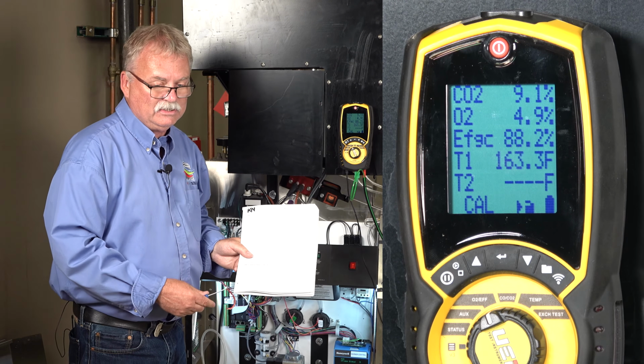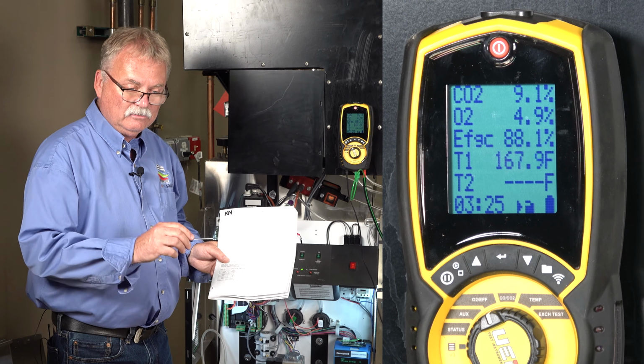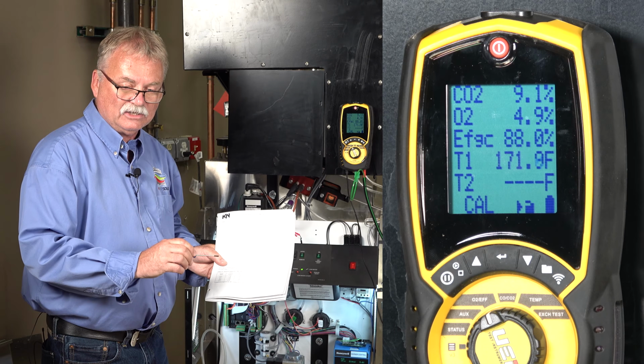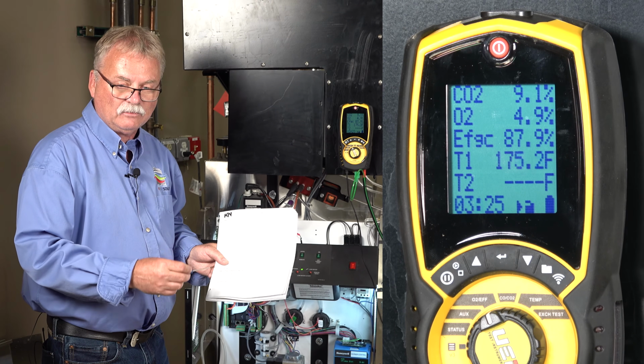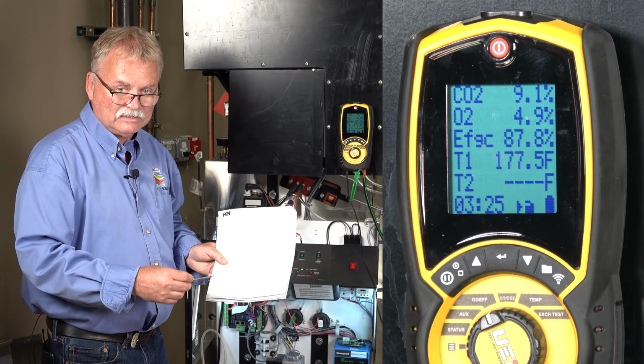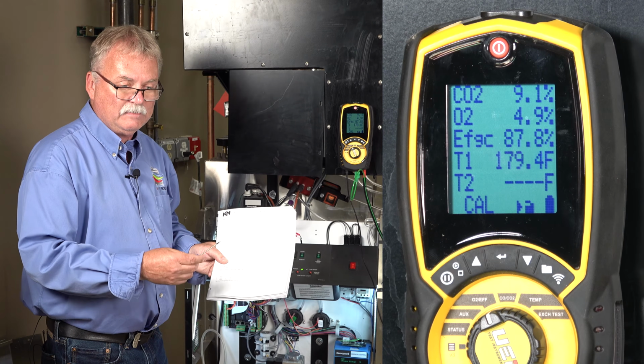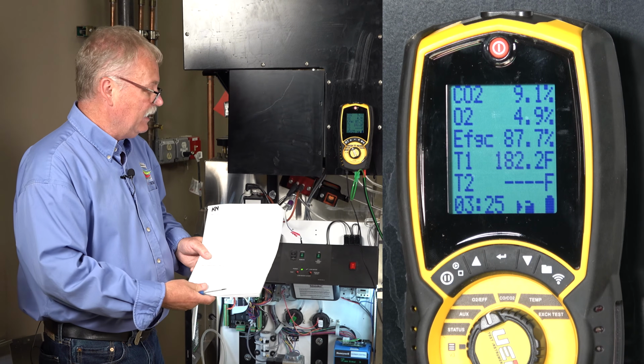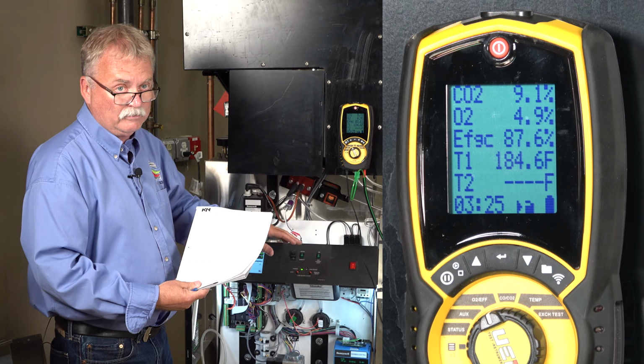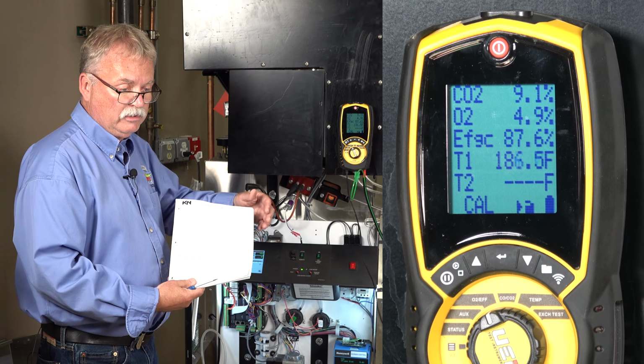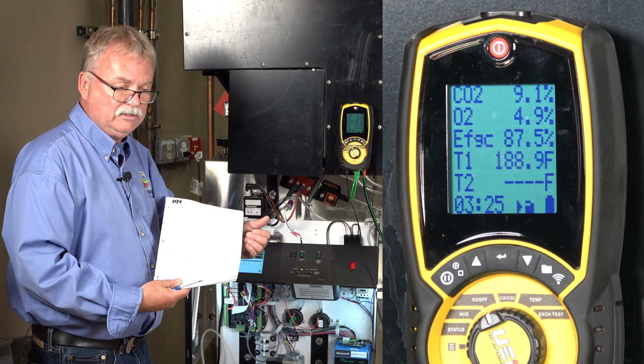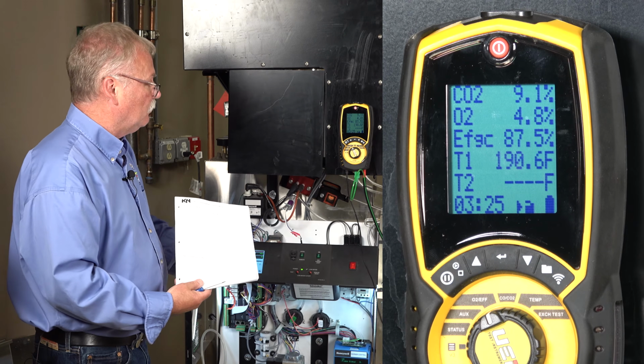When you're doing combustion testing, this is not 5 seconds, 10 seconds, 5 seconds, 10 seconds. You're going to have to wait a minute or two every time, sometimes 3 minutes. It all depends on the size of the system and the responsiveness of the boiler. The bigger the boiler gets, the slower it is going to be to respond. So be patient.